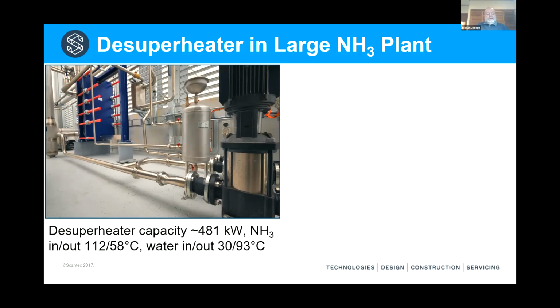So again here, the plate heat exchanger you see in that picture was probably $20,000, but the capital cost of the entire system, if we include the 7.5 cubic metre insulated water storage tank that serves as a buffer, and all the other auxiliaries around it, the price climbs to about $120,000 to $150,000, depending on the extent of the pipe work and so on. So the heat exchanger itself is kind of a small thing in the scheme of things.